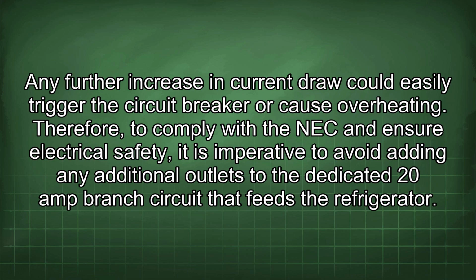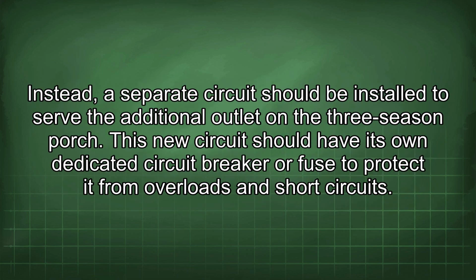Therefore, to comply with the NEC and ensure electrical safety, it is imperative to avoid adding any additional outlets to the dedicated 20-amp branch circuit that feeds the refrigerator. Instead, a separate circuit should be installed to serve the additional outlet on the 3-season porch.